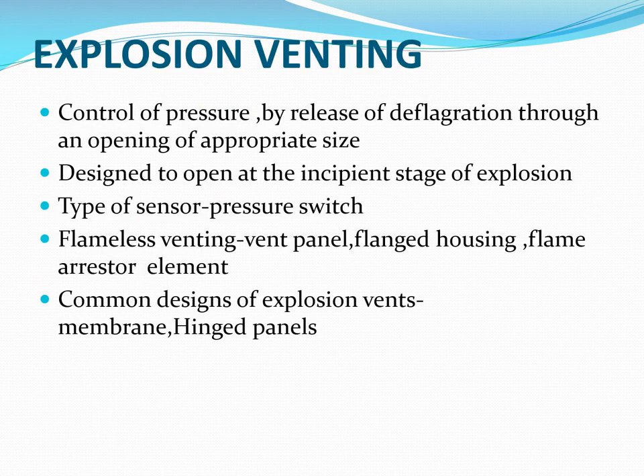Explosion venting is the control of pressure by the release of deflagration through an opening of appropriate size. Deflagration consists of a rapid reaction during which heat is transferred from a reaction zone to nearby reactants, raising their temperature until they too react. Explosion venting systems are designed to open at the initial or incipient stage of an explosion, using pressure switches as sensors. In flameless venting, the key components are a vent panel, flanged housing, and a flame arrester element.